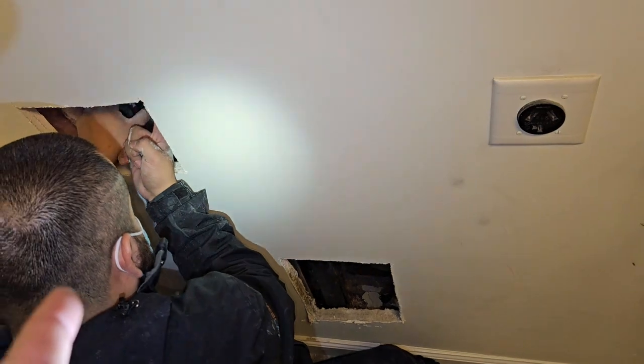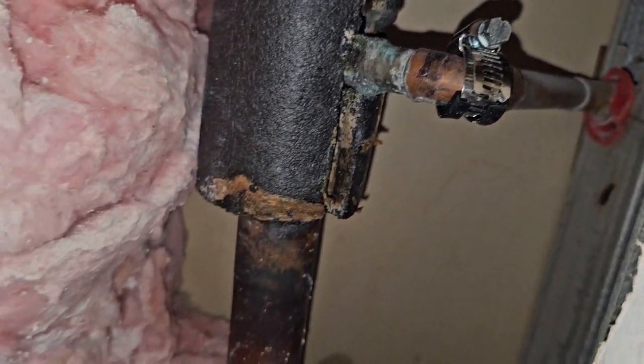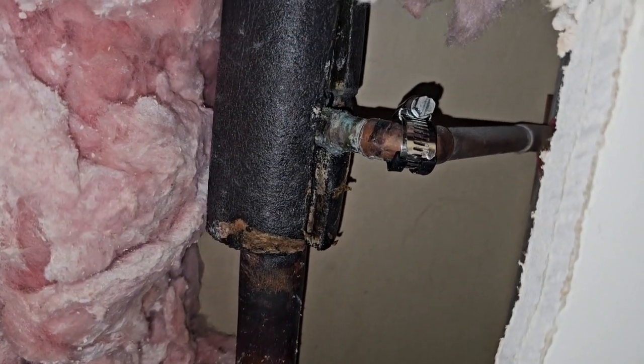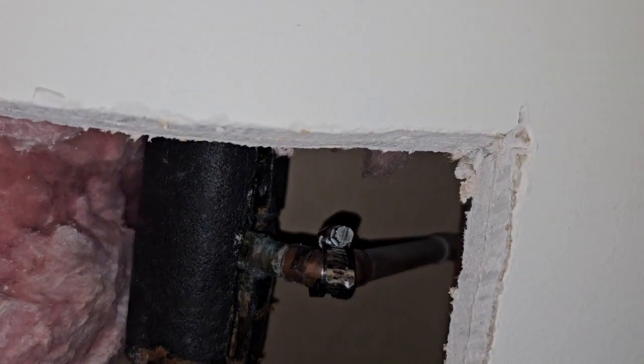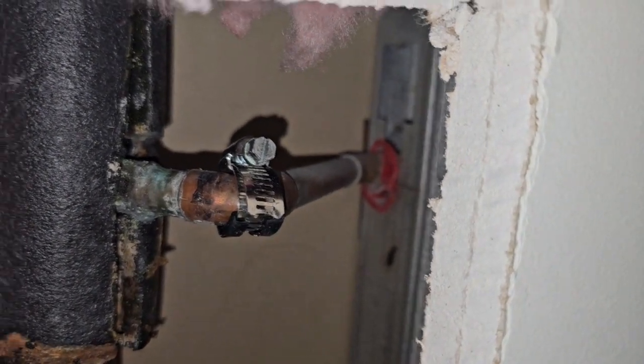So you can see how we use that thermal camera and some other tools in order to kind of locate these leaks behind the wall. So here we got a temporary clamp on the pipe. We're going to end up having to shut the water off for this tier and replace this T and the 45 that goes back in the wall, that half-inch line there. But that will be another day.